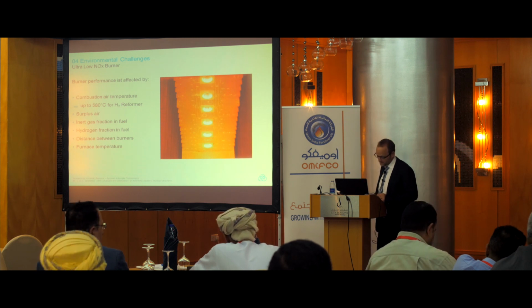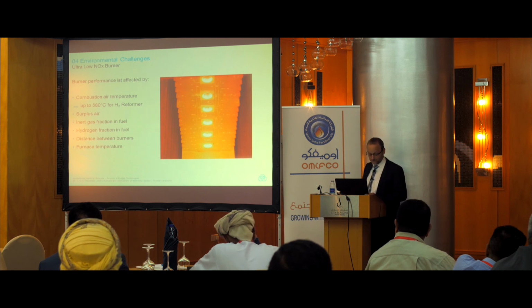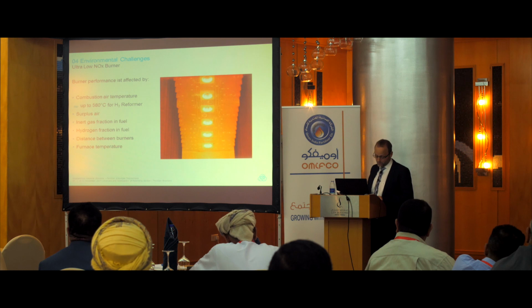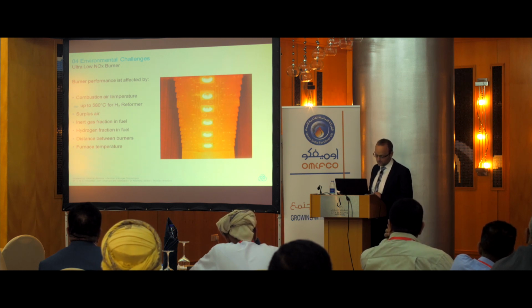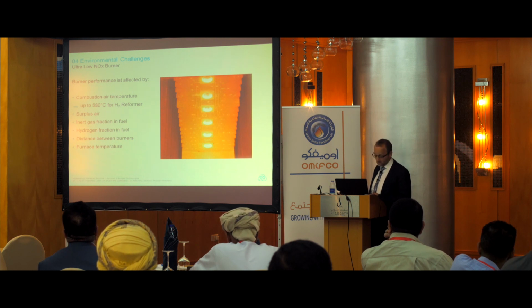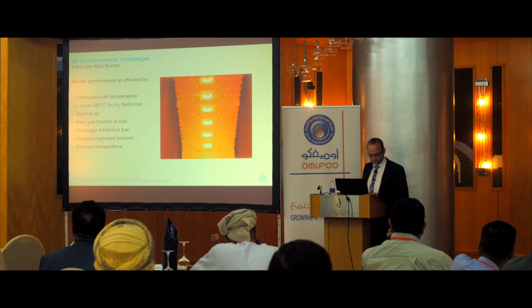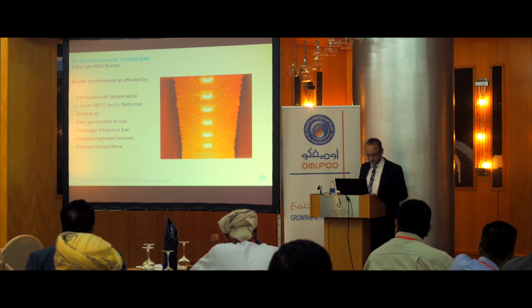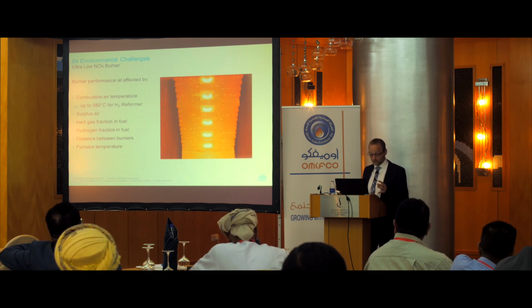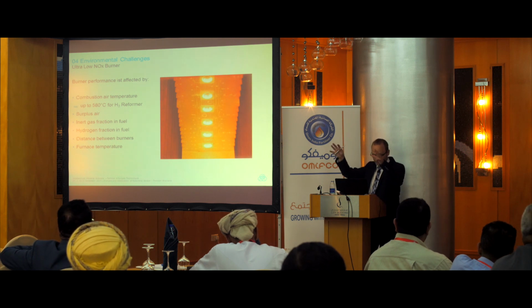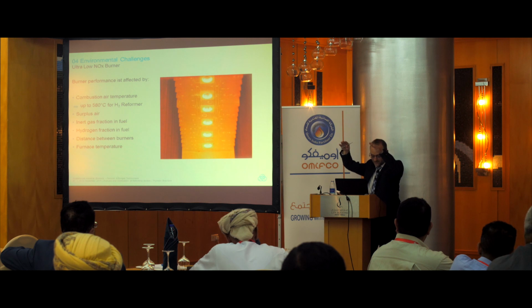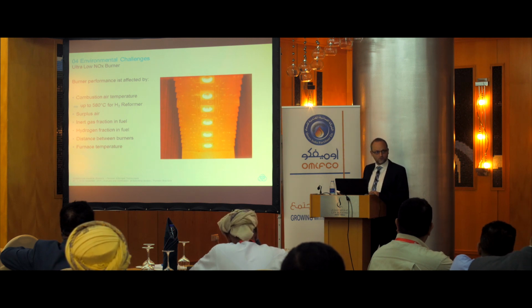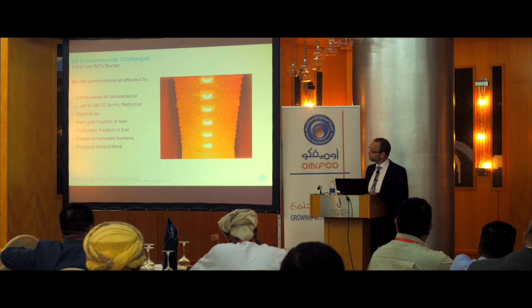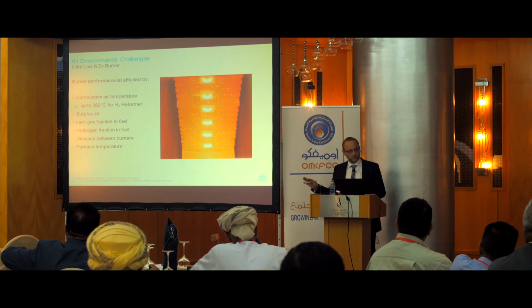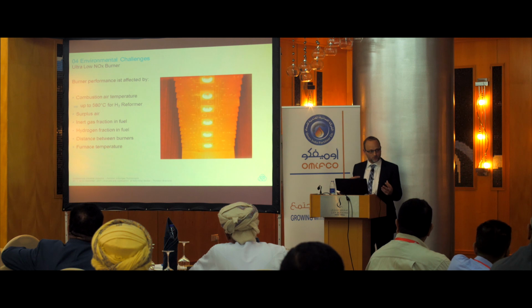The different burners available in the market can be classified into air stage and fuel stage burners. For each type of burner, several reaction zones will be created, which will lower the flame temperature and therefore reduce the thermal NOx created in the flame. In addition, ultra-low NOx burners can be characterized by the significant flue gas recirculation. So a part of the flue gas from the burner will be re-entrained into the burner itself, and with this further significant NOx reduction is possible. However, a further reduction will be more and more difficult because next to the thermal NOx which will be created within the flame, you have also chemical NOx, and these we cannot avoid.